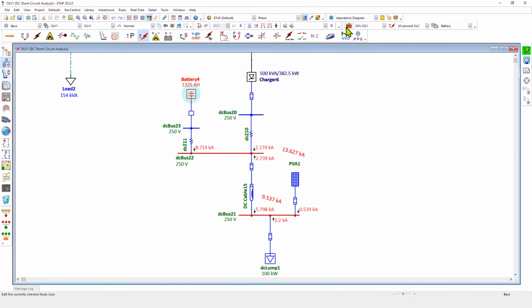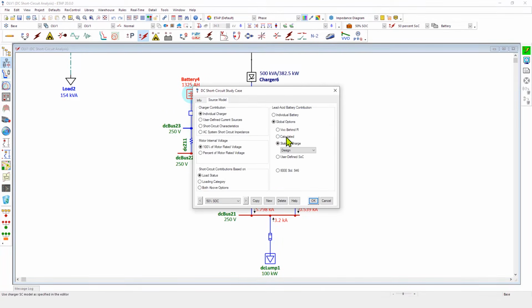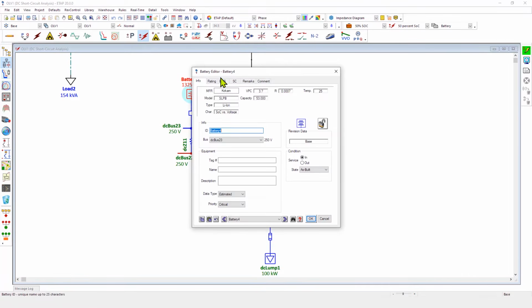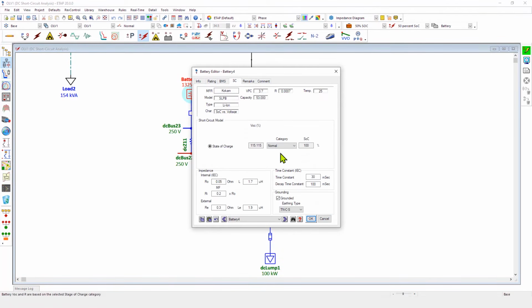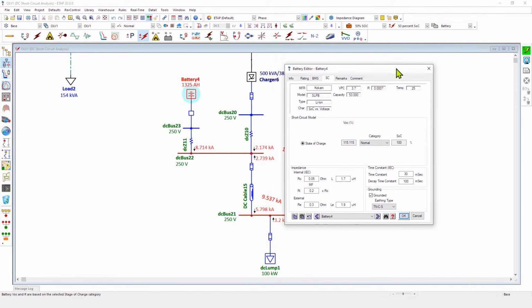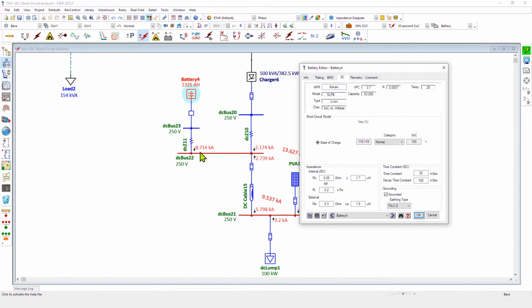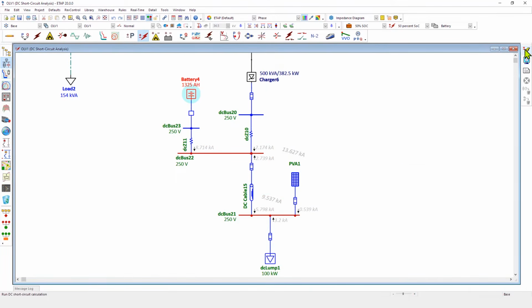So we can go ahead into our short circuit study case and set up the battery to use variable state of charge. The first state of charge that we would like to use is normal, where the state of charge is 100%. And we can observe that based on that state of charge, the contribution from the battery is 8.7 kiloamps. If we set the state of charge to 50%, we can observe that the fault current contribution changes to a lower number, which makes logical sense.